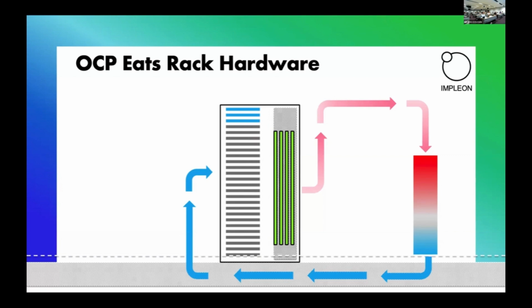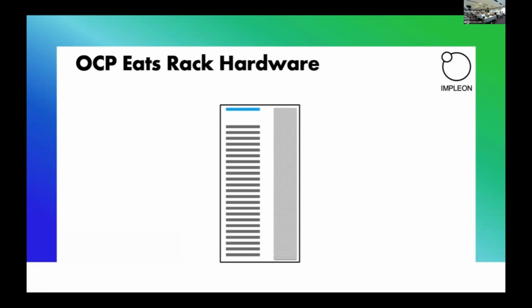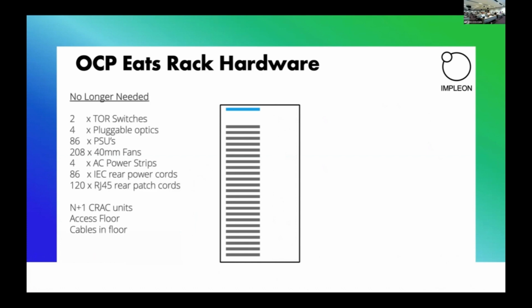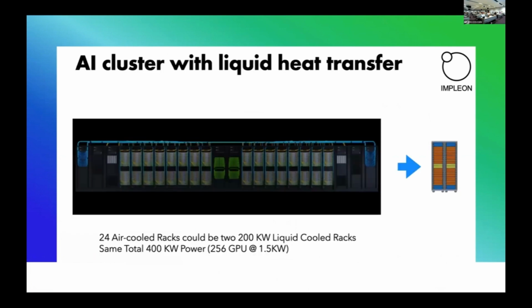It means that we take away all the power supplies from the servers. Next thing is that we have one switch instead of 3 in the rack. We take away the PDU because we use one electrical bus bar. We don't need raised floors, without raised floors, without CRAC units. And in the end, we take away all these components from the rack. This is why it's less expensive and less carbon intensive. Next one is about AI.